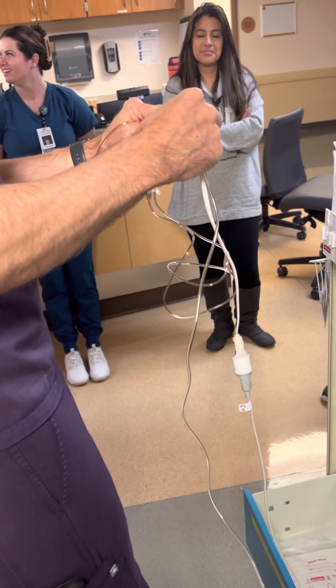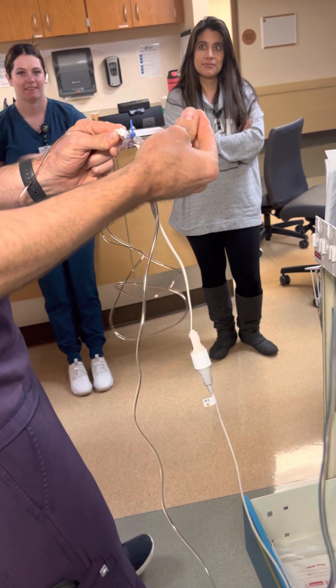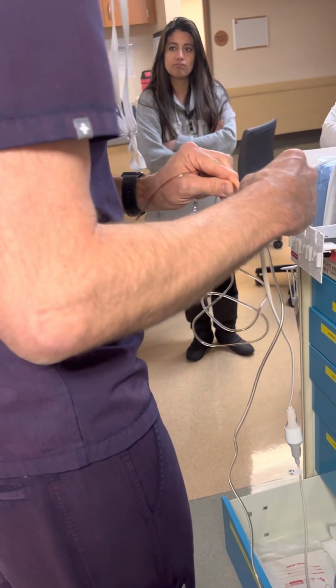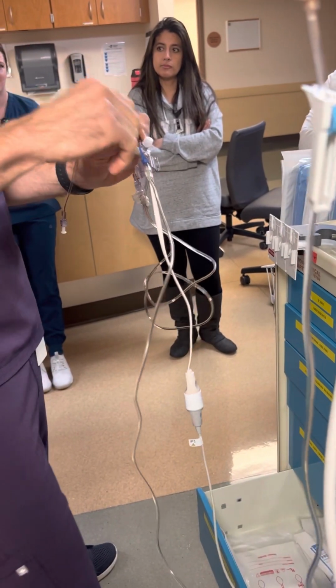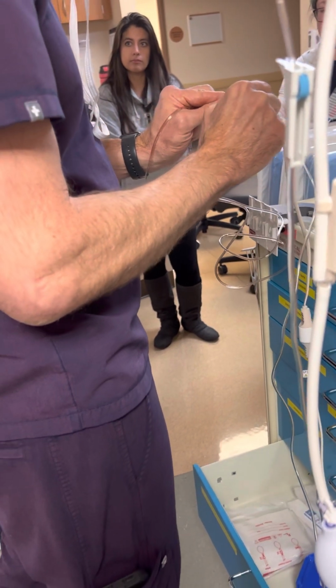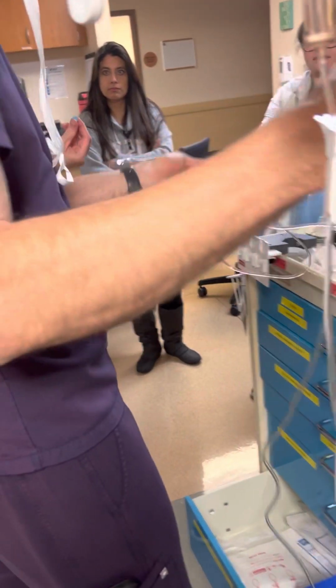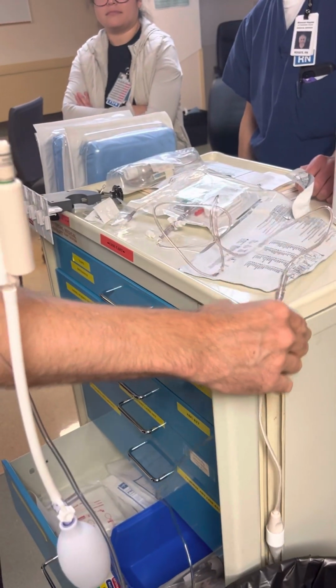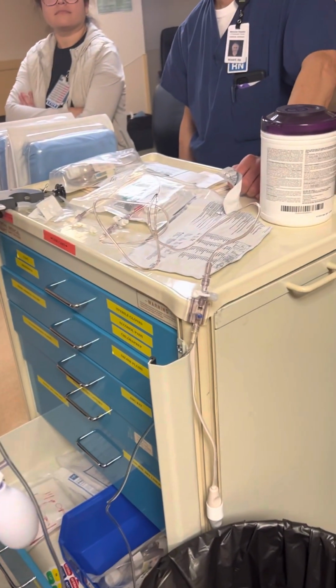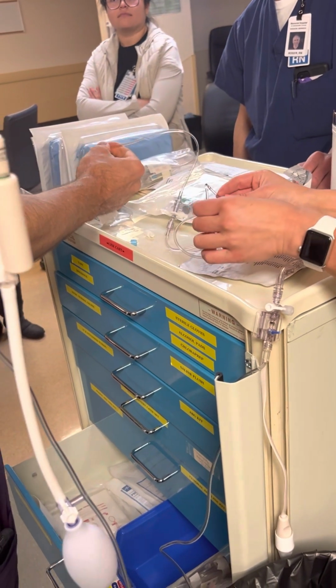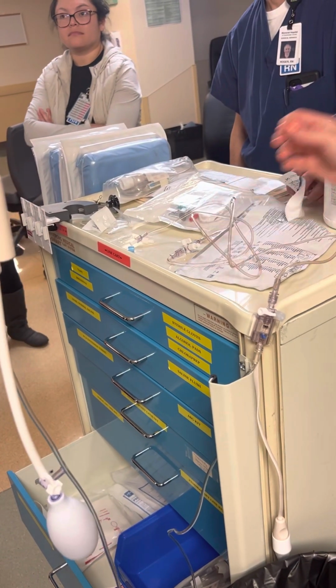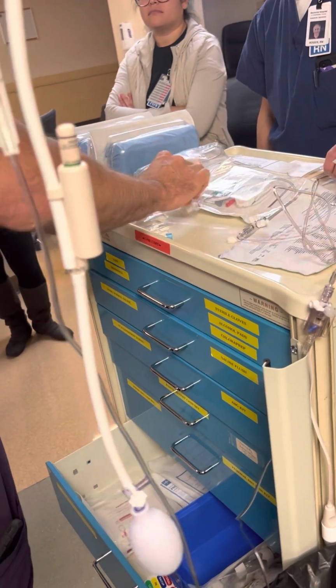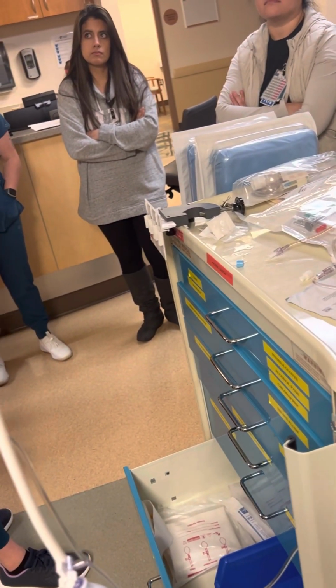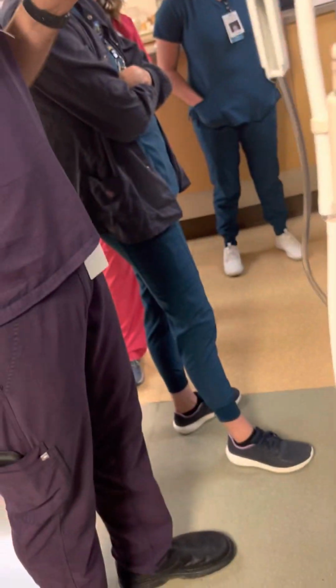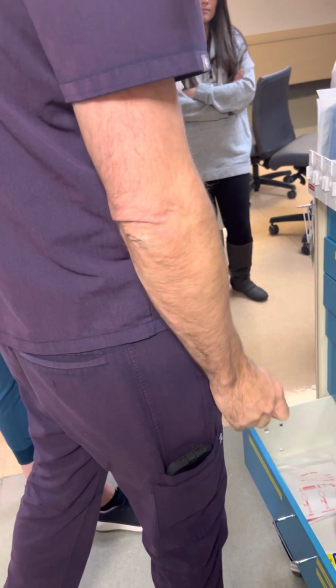Turn it off to the patient. Make sure that there's either a cap that breathes, or you can take the cap off and read the pressure of the air. Zero it. It has to be a breathable cap. Once it's zeroed, you can turn it so that it'll read the patient's pressure. Sometimes you have to flush arterial lines because the end of the catheter is caught on something, but you can usually see that as the tracing starts to dampen. Then you question if the patient's pressure is dampening, going down, or if it's just monitor error.